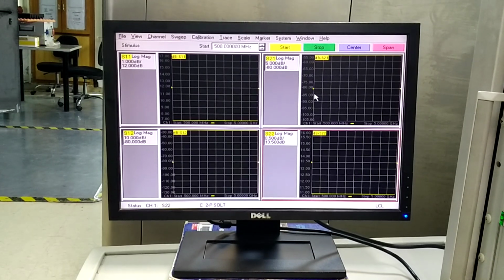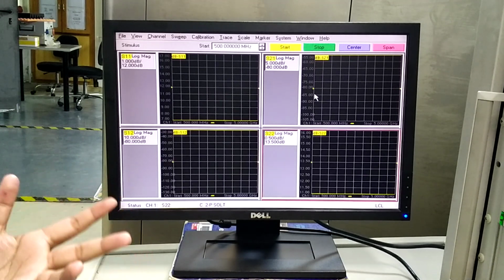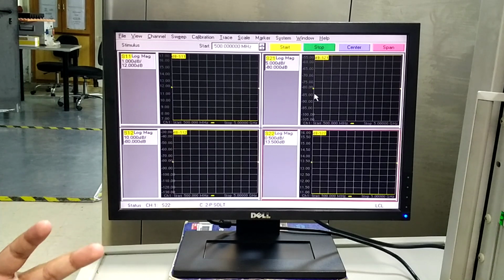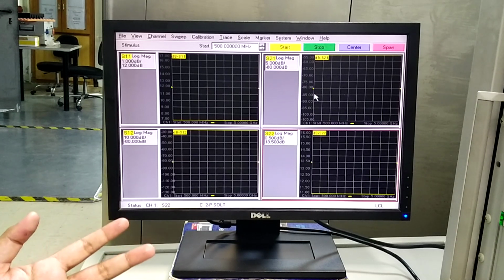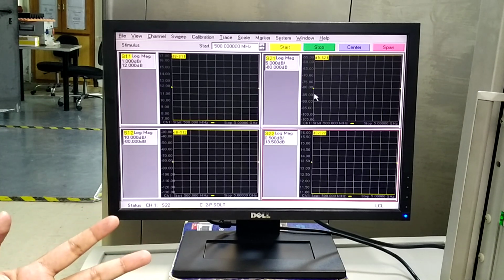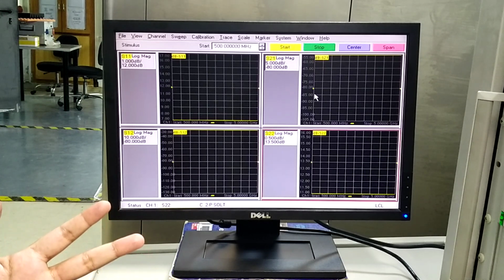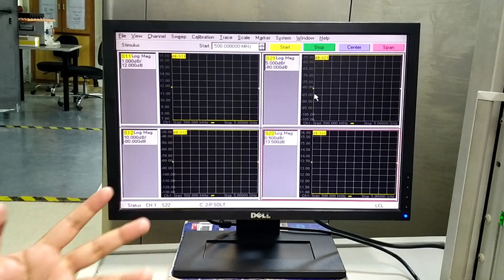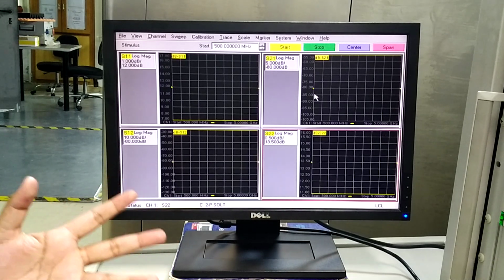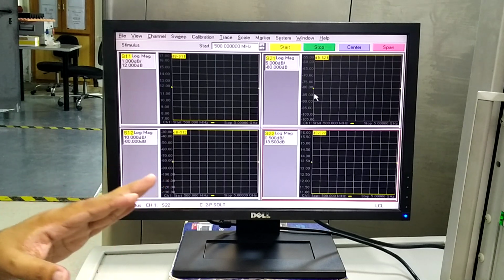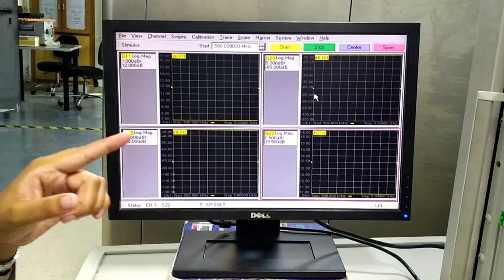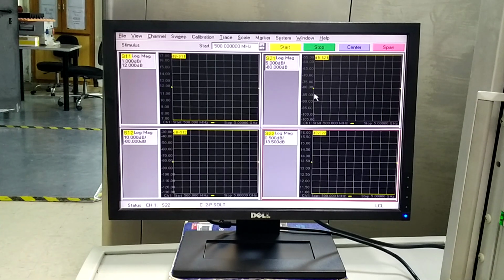Once you perform the calibration, the next important thing is how to validate the calibration. How do you know that you have performed the correct calibration? For this purpose, one of the standards we use, one of the DUTs, is one that has a known response. For example, I can use an attenuator. Since I know this is, let's say, a minus 10 dB or minus 20 dB attenuator, I know that it has a minus 10 or minus 20 dB S21 or S12. So if after my calibration this attenuator displays the same thing that is meant for this attenuator in its data sheet, it means I performed the correct calibration.